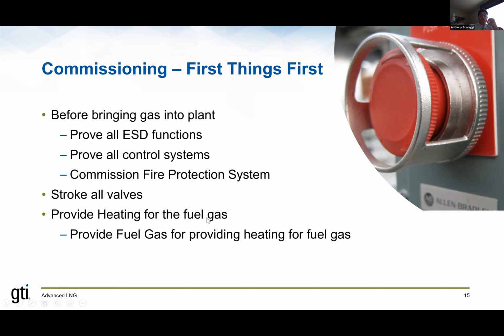When you provide your own fuel gas, generally it has to be heated up, because as we know, LNG is cold. And when you take LNG gases, or any gas, and it's a pressurized gas, and you're reducing in pressure very quickly, you get a cooling effect. And so that gas needs to be warmed up before it can be used as a fuel. So you need to provide heating for the fuel gas. And, as a little joke down here, sometimes you need to provide fuel for heating the fuel gas, right? So you have to figure out how you're going to do that. How are you going to have fuel to heat your fuel gas before you have fuel gas, right?